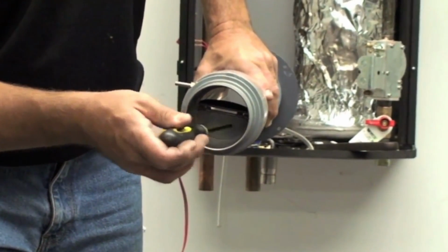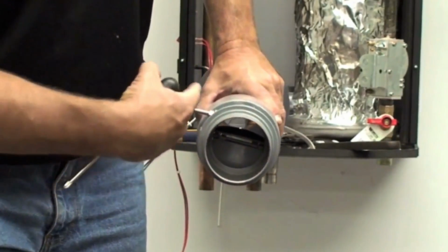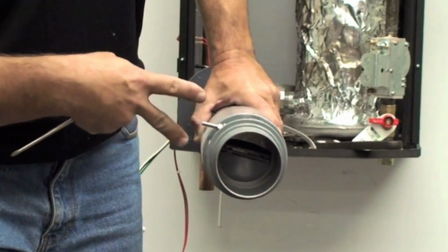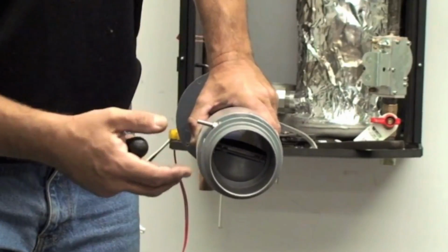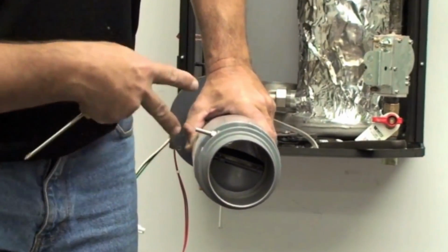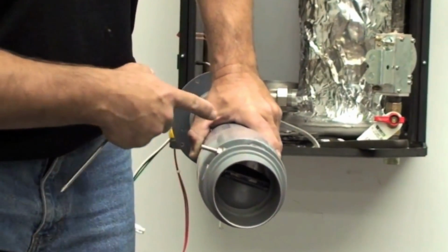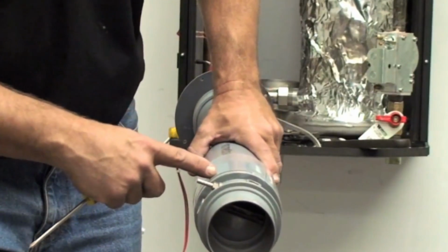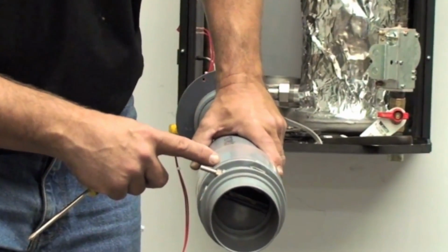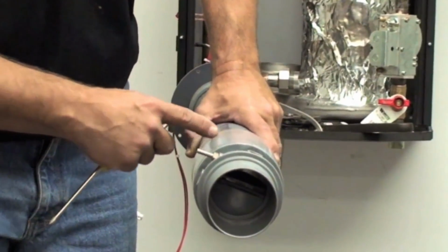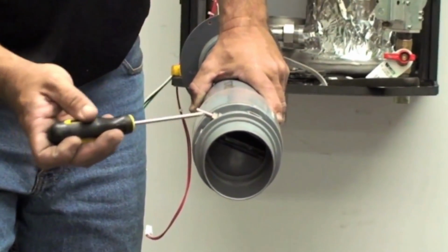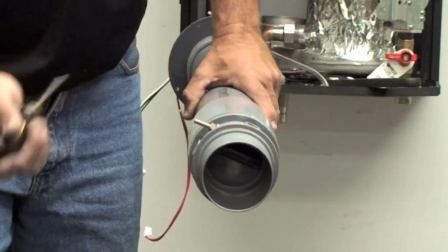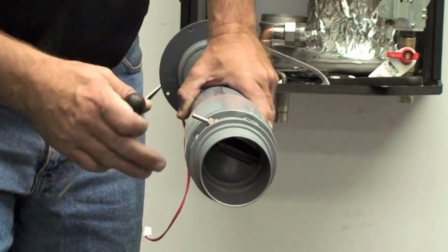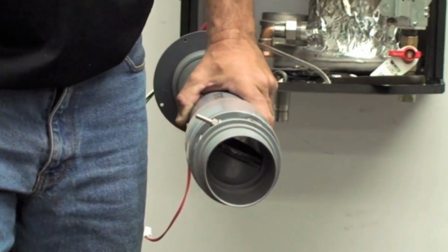But what happens is as the fan runs, airflow is in this direction, it lifts the flappers, and then when the fan is disengaged and there's no airflow, the flappers close, and it keeps any air from moving back into the system, cold air, during the winter time where you start having some convection, and it'll eliminate any possible contaminants getting back into the boiler. That'll help all the components of the system last longer.